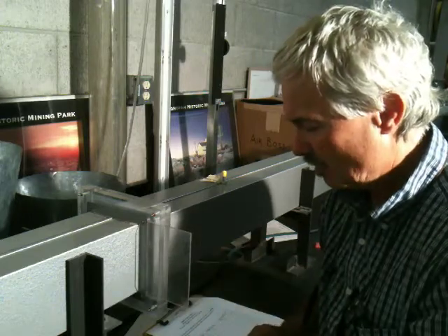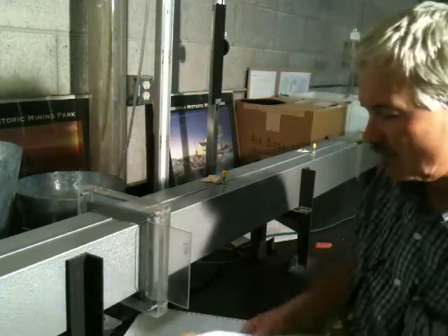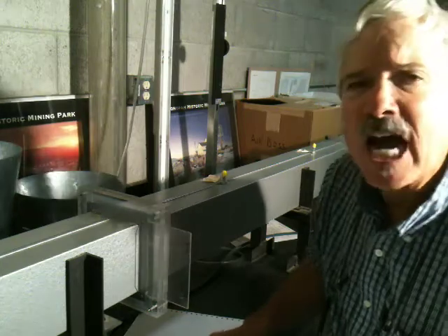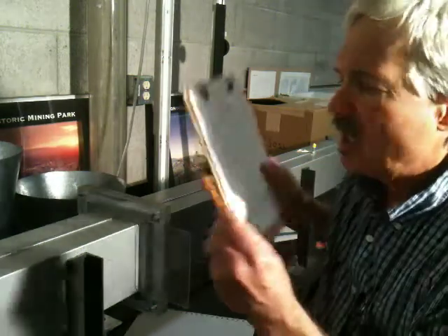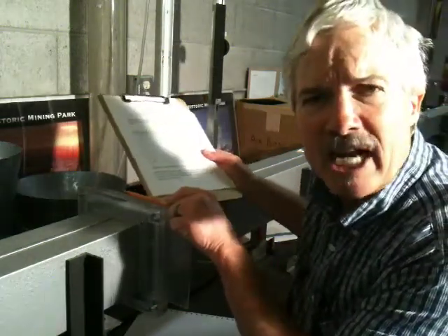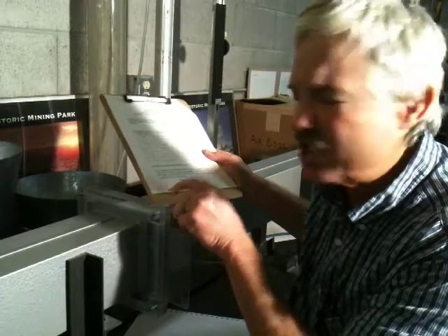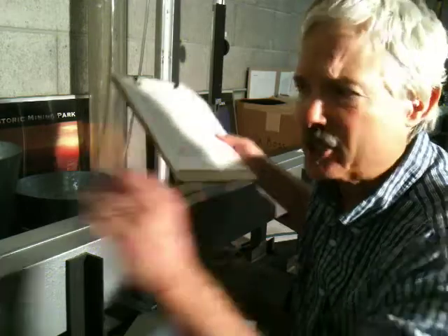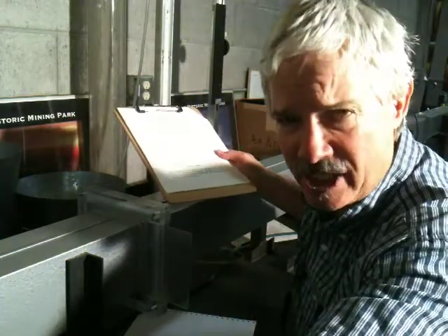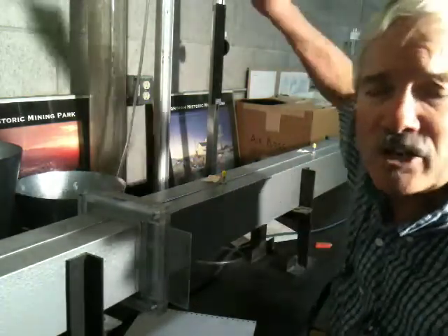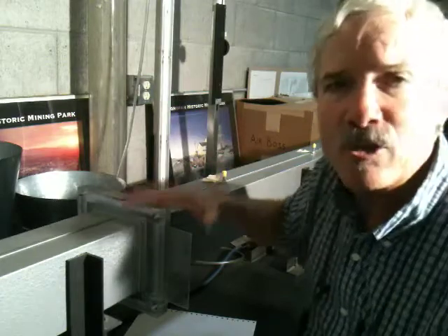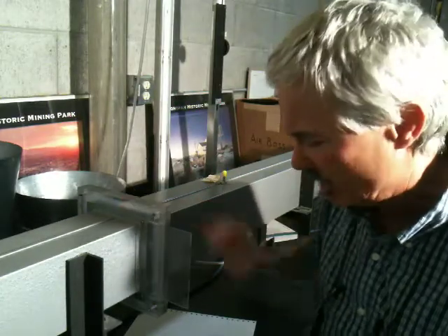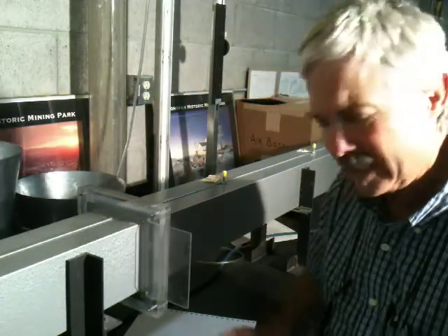Now this time, the pressure drop is happening right here at the regulator station. So as we put in these increasingly smaller regulator sections, our pressure drop is actually going to increase here. Previously, when we did the P equals RQ squared exercise, the delta pressure decreased downstream from the flow restriction. Okay, so we'll go ahead and take this.